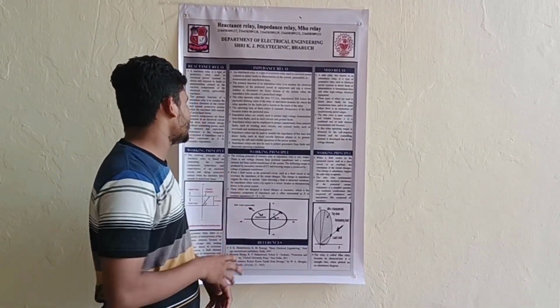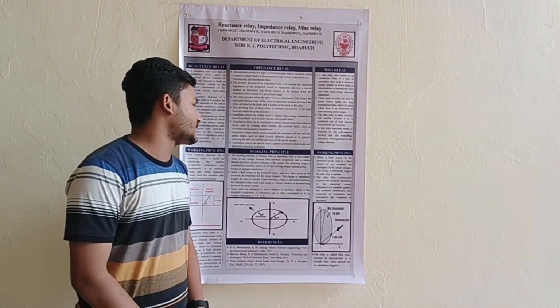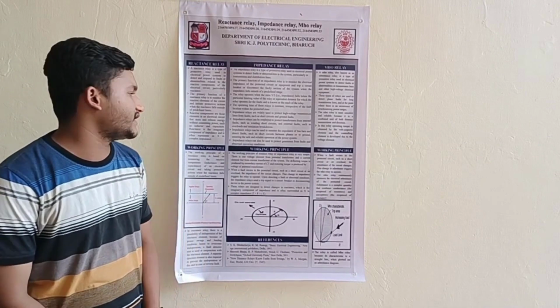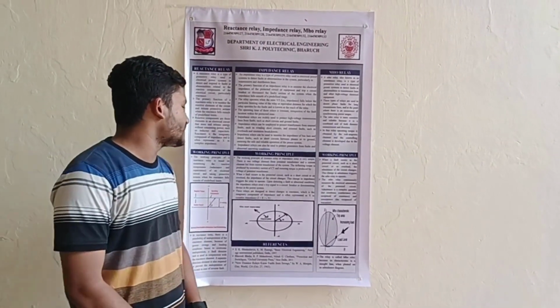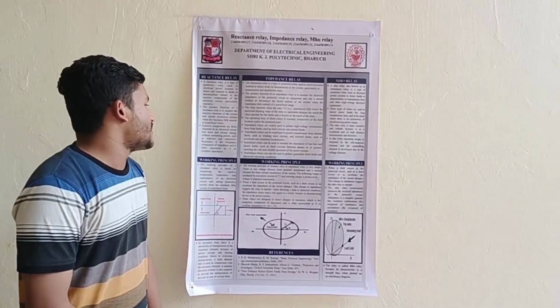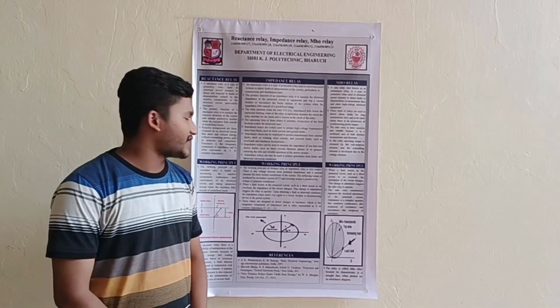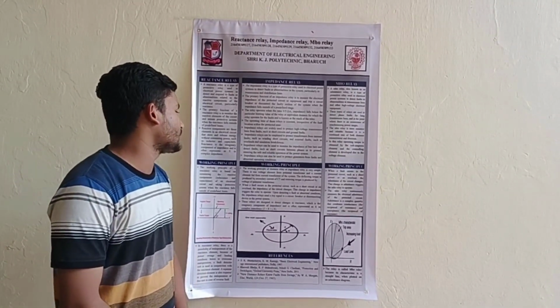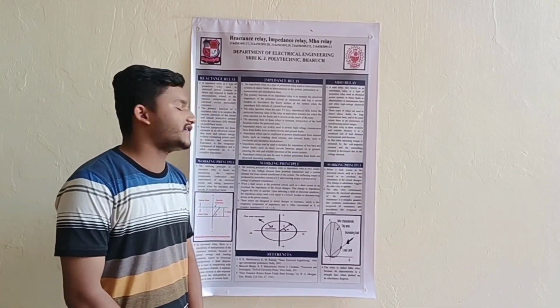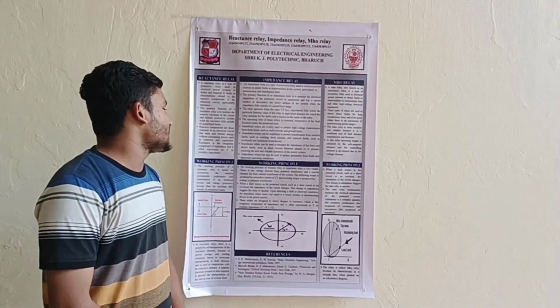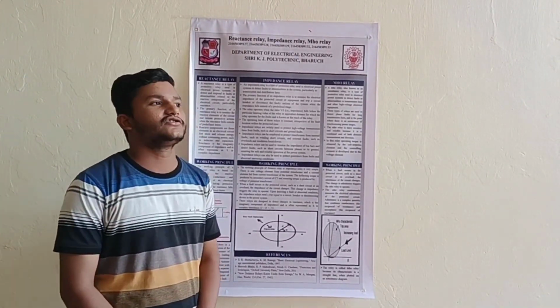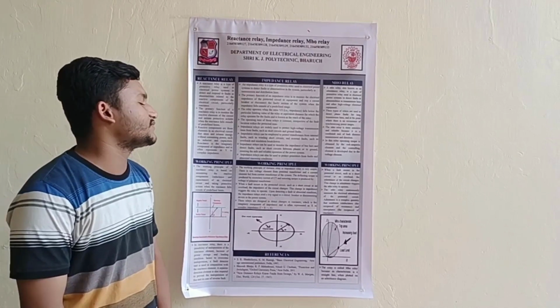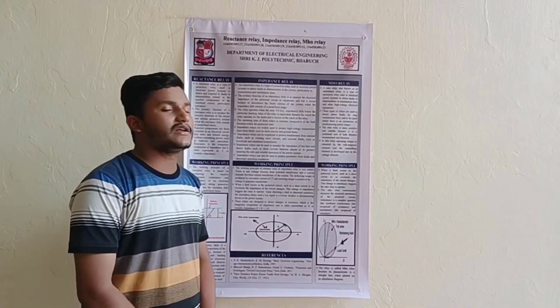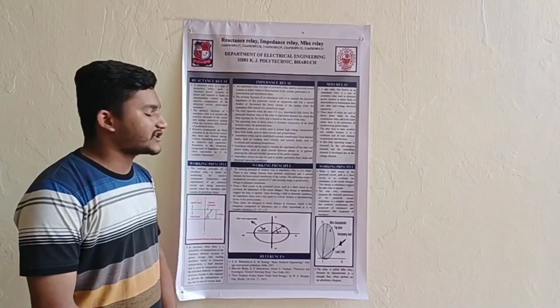Impedance relay working principle. The working principle of distance relay or impedance relay is very simple. There is a one voltage element from potential transformer, a current element fed from current transformer of the system. The deflecting torque is produced by secondary current of CT and restoring torque is produced by voltage of potential transformer.